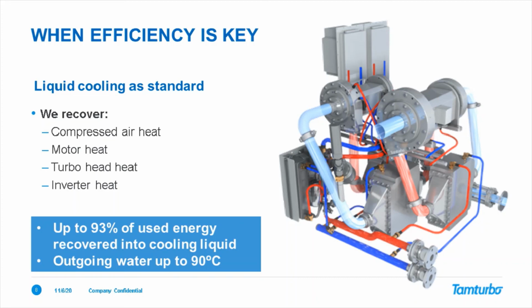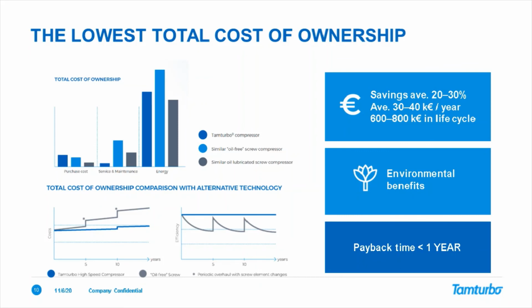Thank you, Thomas. It seems that Tamturbo is a competitive solution against oil-free compressors. Is it competitive against typical oil lubricated compressors? From a cost point of view, yes, it takes a little bit longer for the payback, and the compressed air quality comes in a slightly different way. We do have multiple customers who have traditionally used oil lubricated screw compressors. The energy efficiency of the oil lubricated screw compressor itself is quite good. But when you take into account the added pressure drop of the oil filtration, then in some cases we are actually better in energy efficiency before the dryer.